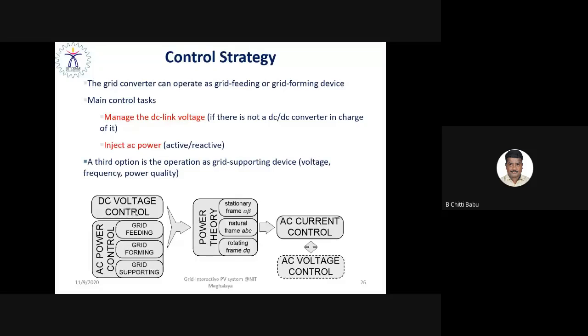With the help of this theory, in terms of the stationary reference frame in alpha beta, or the natural reference frame in ABC, or the rotating reference frame in DQ, we are able to handle both AC as well as DC parameters. Still, we can make it linearized, right? So, AC power control and the grid converter can act as a grid feeding device or a grid forming device, managing the DC link voltage. If there is not a DC to DC converter in charge of it, it can still inject controllable AC power into the utility grid in terms of active as well as reactive power. The third option is operation as a grid supporting device in terms of voltage, frequency, or power quality.